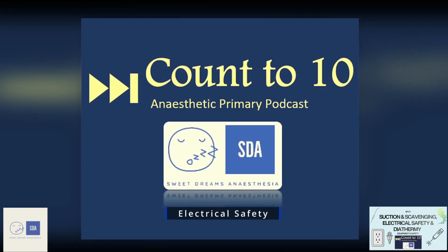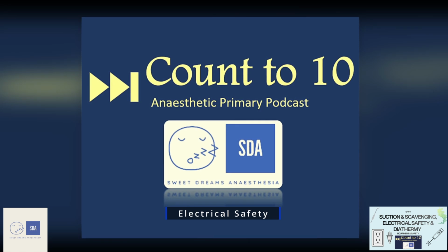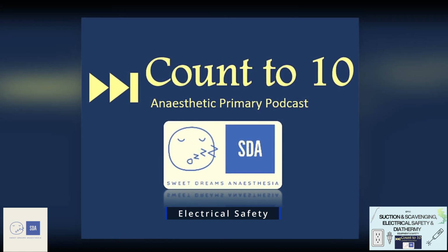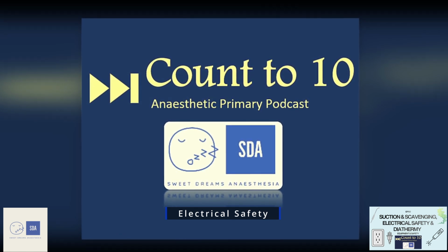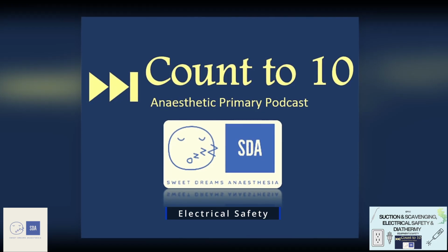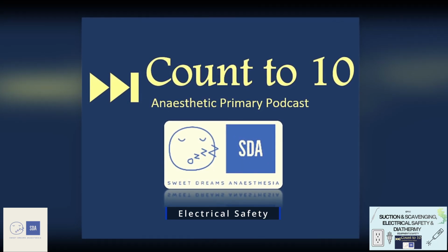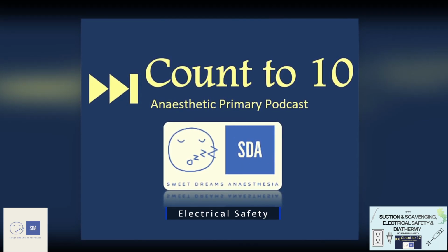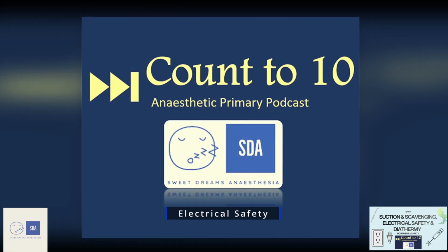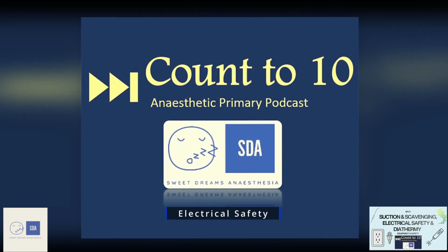And when this occurs, instead of shutting that circuit down like an RCD does, the LIM instead will set off an alarm to let you know that there's a breach or a leak in the circuit. And the threshold for setting off that alarm is a current leak above 5 milliamps.